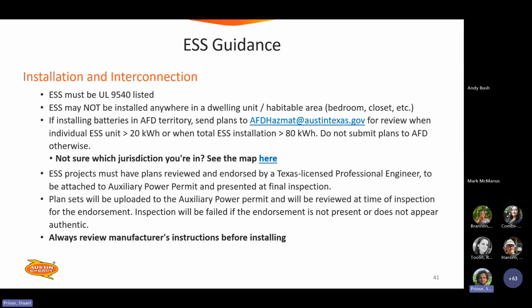ESS projects must have plans reviewed and endorsed by a Texas licensed professional engineer. And this needs to be attached to the auxiliary power permit and presented at final inspection. We can receive that in digital form too at final inspection, but ultimately it just needs to be on the permit. So the plan set will be uploaded to the aux power permit and will be reviewed at the time of inspection for the endorsement. And it'll be a fail if you don't have that endorsement at the time of inspection. And as always, review manufacturer's instructions before installing.